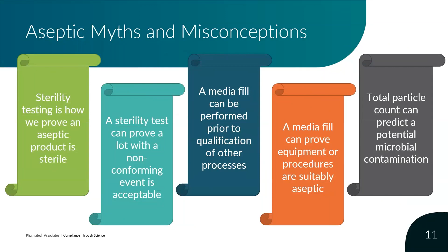Just to underline what we were stating before with these myths and misconceptions, I like to look at aseptic processing as a pyramid. We don't rely solely on that sterility test, we don't rely solely on that media fill. Over-focusing on those upward elements is essentially ignoring the fact that they really only have value because there are underlying controls in place. There's a whole series of systems, controls, and processes that have to be in place in order for us to rely on sterility tests and media fills.